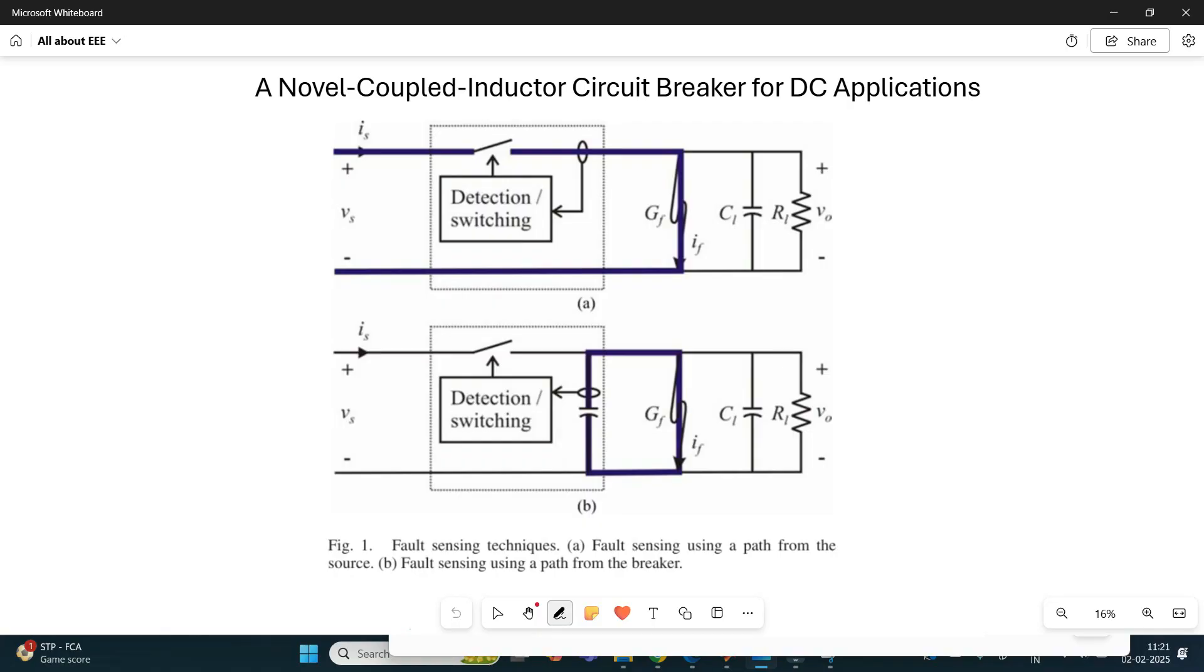Here, we can see two types of fault sensing techniques. First one shows a typical arrangement of circuit breaker inserted between source and load. In this circuit, the source current is monitored for fault current detection. Alternatively, a capacitor can be connected to ground within a breaker in second technique. Actually, the second method is good for detecting transient currents and is used in motor drives for detection of shoot through.